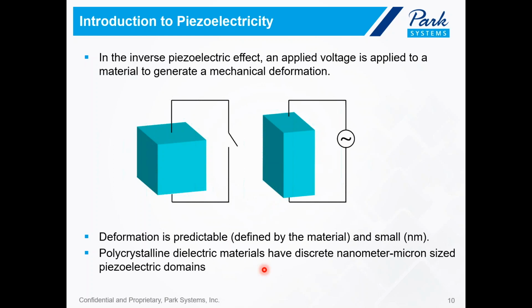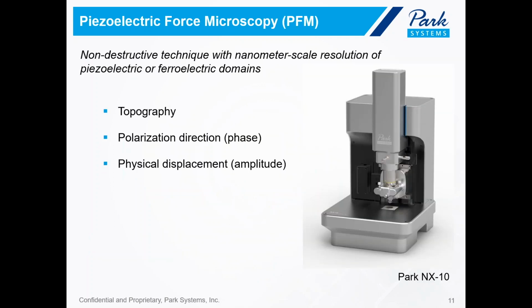And that brings us to atomic force microscopy, AFM, and piezoelectric force microscopy, PFM. PFM is really a non-destructive technique that has nanometer scale resolution, and it allows us to characterize these piezoelectric and ferroelectric domains at the nanometer length scale without having to sacrifice your sample, without putting any damage to your sample, ideally.